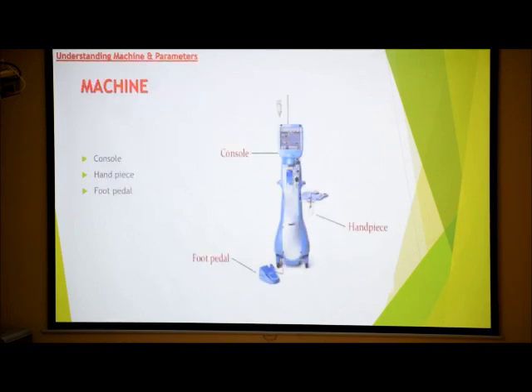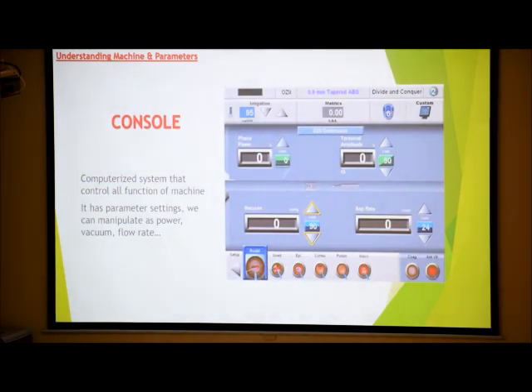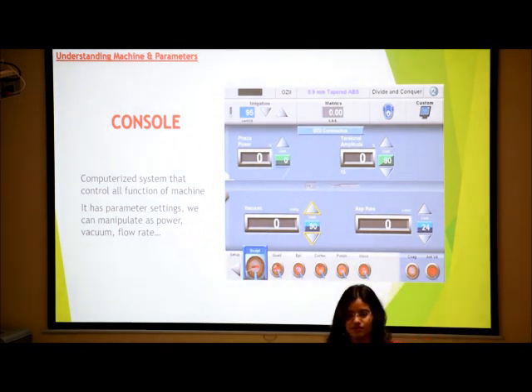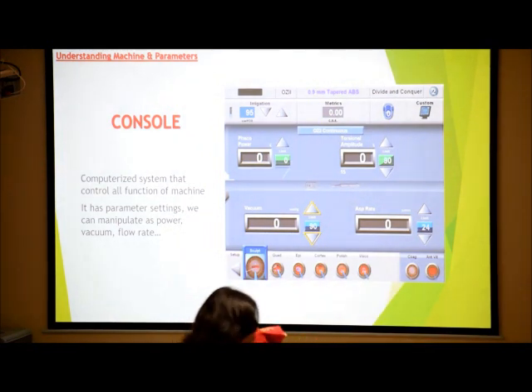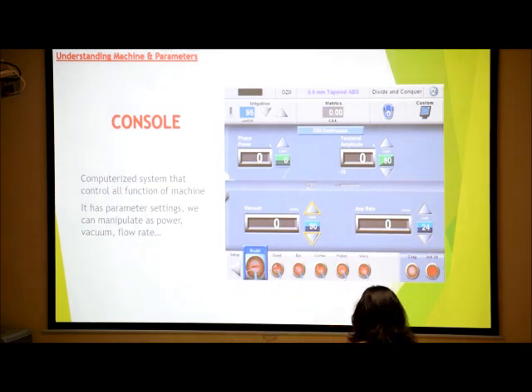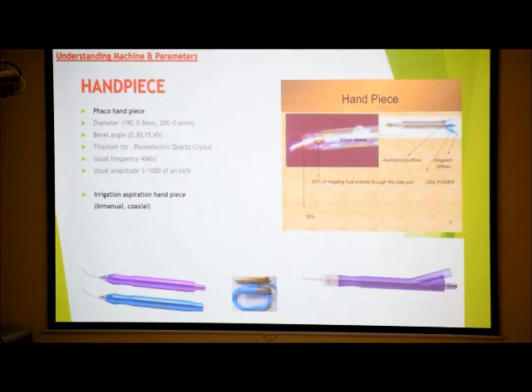So this is the machine which has got three parts: one console, handpiece, and foot pedal. Console is a computerized unit which deals with manipulating parameters which are basically the power, the vacuum, and the flow rate. Handpiece is a device which delivers the power into the eye, helps in breaking down the crystalline into pieces, and also aspirate the emulsified pieces out of the bag, out of the eye.